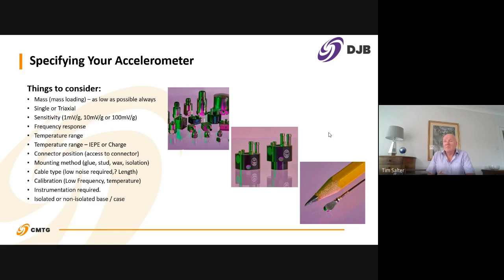Single or triaxial, which directions do you want to be measuring in? What's the sensitivity you need? The normal ones are either 1, 10, or 100 millivolts per G, and that's highly dependent on the maximum acceleration level you're likely to see. What's the frequency response? What temperature range do you need? Because that dictates whether you have IEPE or charge. Where do you want the connector? So access to the connector, is that top or on the side, which I've got an example of later.